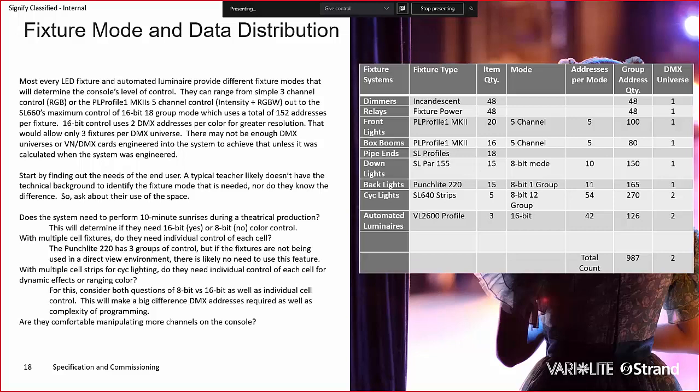I would say typically, if it's a single universe system, our quotes and application engineering department are probably going to keep that all DMX distributed with no network involved. However, if there are multiple universes involved, we're probably going to engineer that with a network. So something to think about.